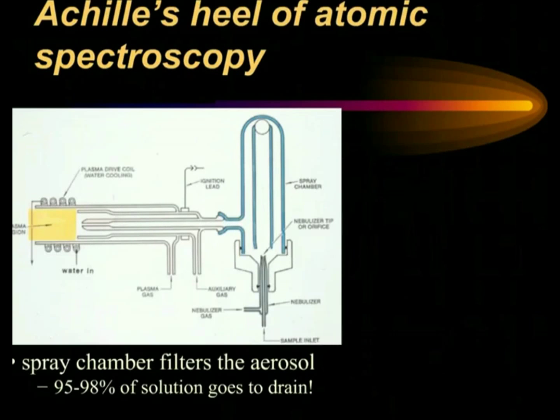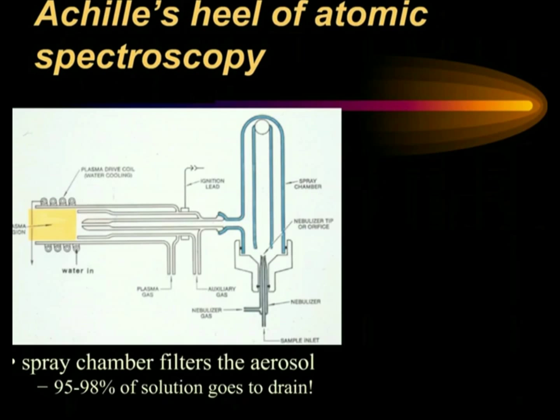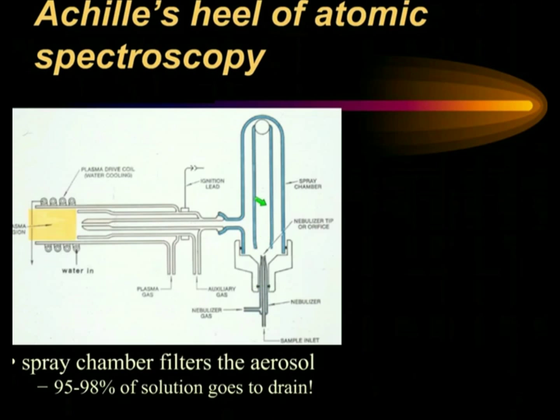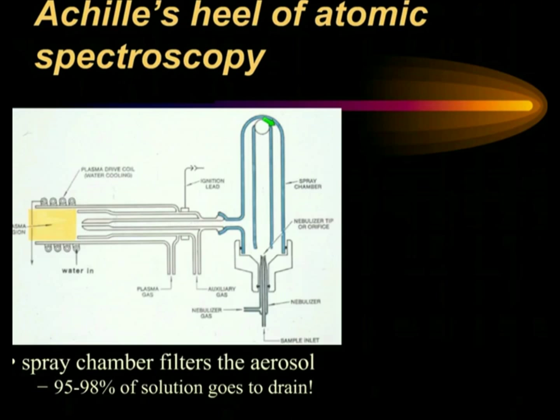Nothing is perfect. ICP spectroscopy has one Achilles heel, and that is the sample introduction system. You see a picture of a typical system here, where you have a nebulizer, a spray chamber, and the aerosol has to go down the central path of what is called a double-pass spray chamber. Most of it drops out into the drain. The finest aerosol then makes its way into the plasma. A key problem with this system is that 95% to 98% of the solution goes down the drain.